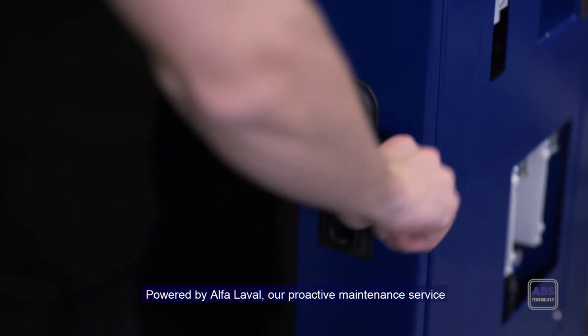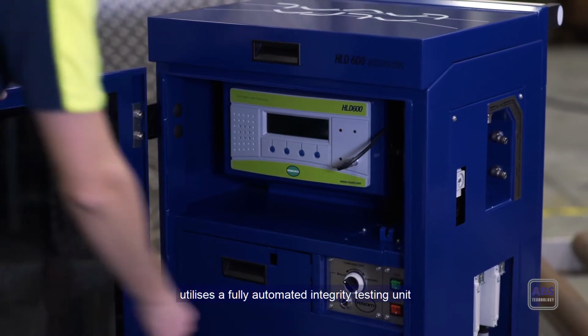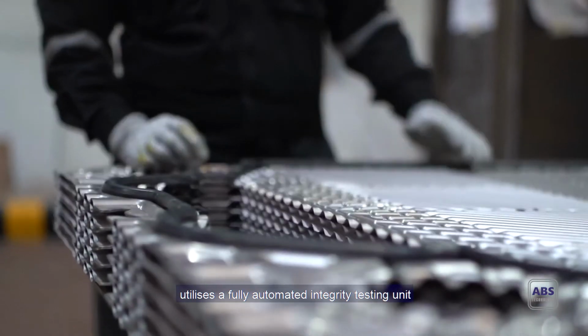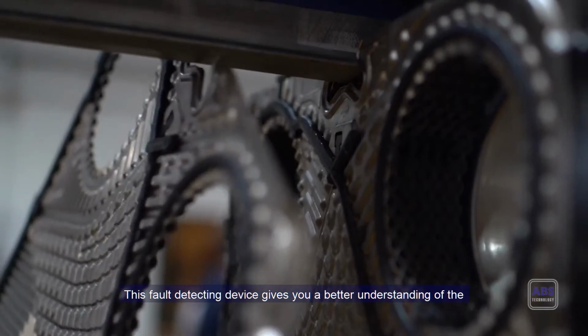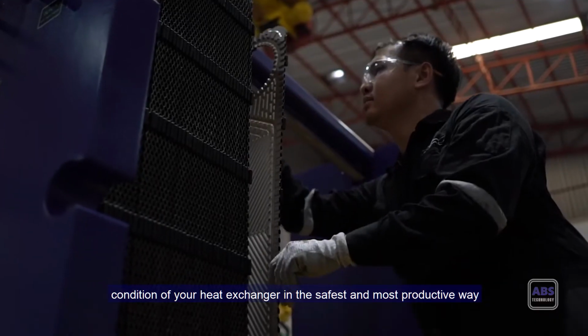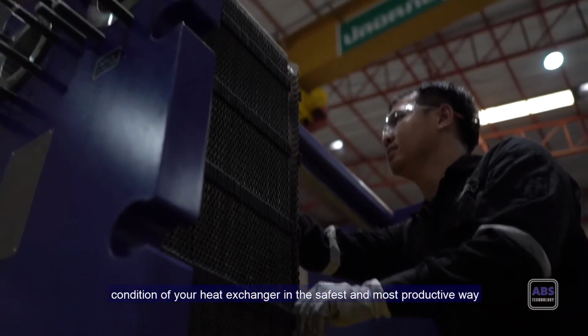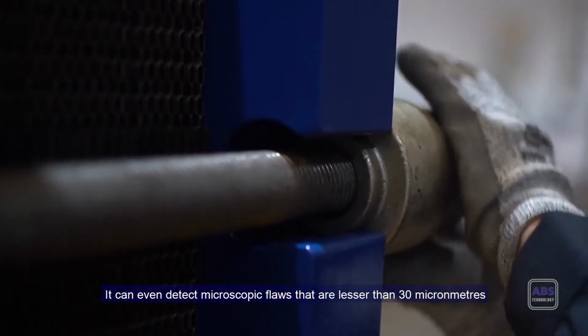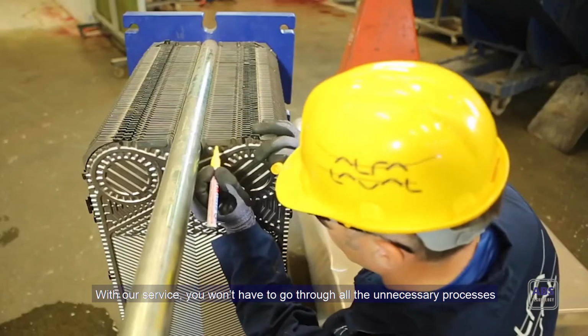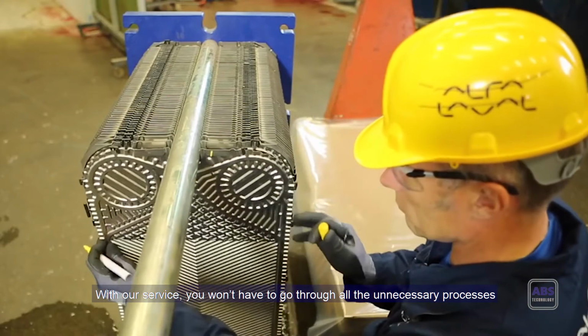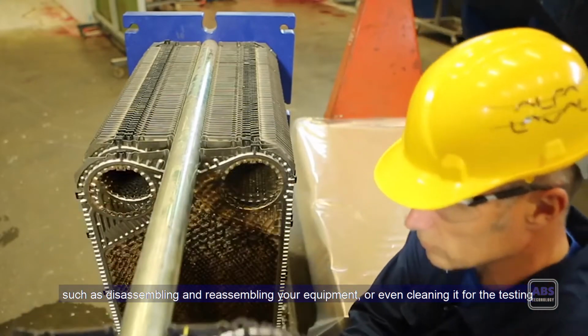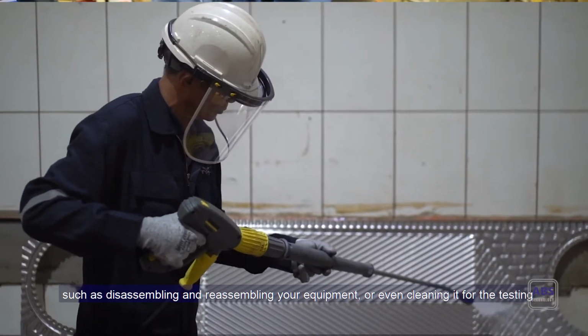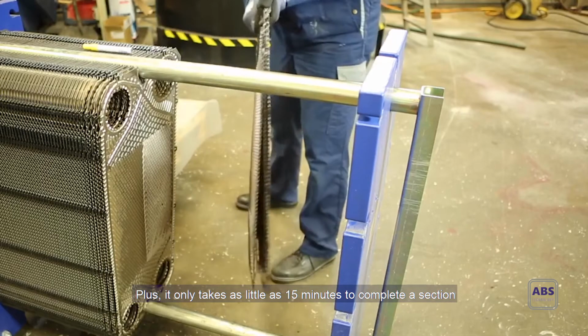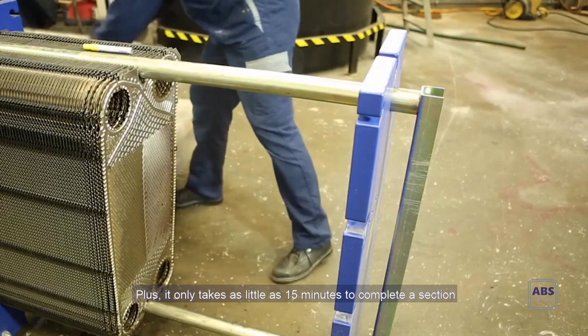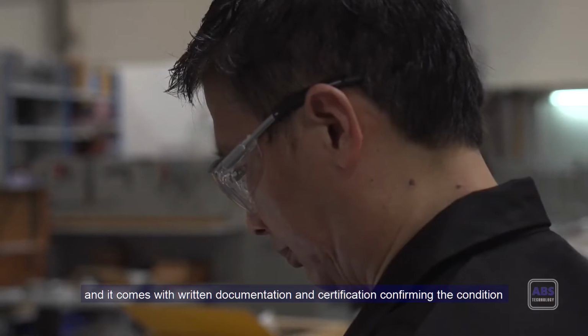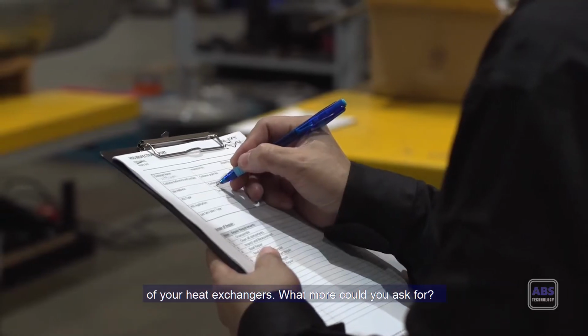Powered by Alfa Laval, our proactive maintenance service utilizes a fully automated integrity testing unit. This fault detecting device gives you a better understanding of the condition of your heat exchanger in the safest and most productive way. It can even detect microscopic flaws lesser than 30 micrometers. With our service, you won't have to go through unnecessary processes such as disassembling and reassembling your equipment, or even cleaning it for the testing. Plus, it only takes as little as 15 minutes to complete a section, and it comes with written documentation and certification confirming the condition of your heat exchangers.